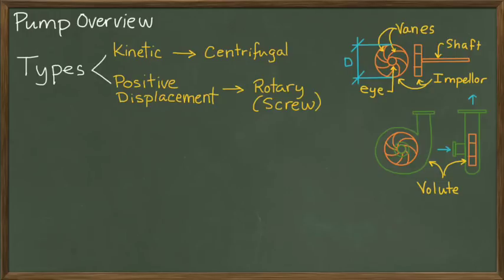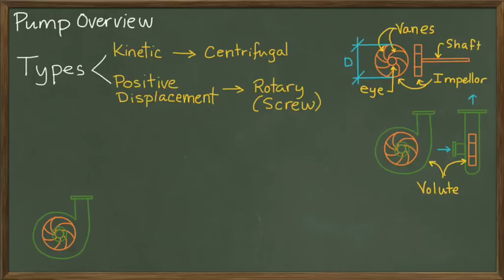There are a couple of important things to realize about a centrifugal pump. When you turn it on, it doesn't simply run at a set discharge or a set pressure head. If we ran this pump with no attached pipe, water would come squirting out the top at maximum discharge. But if we attached a pipe that extended way into the sky, we would reach a point where we just could not overcome the water column height, essentially shutting off flow — the pump would still be rotating, but there would be no flow rate. That's because the weight of the water column now equals the energy being added by the pump.